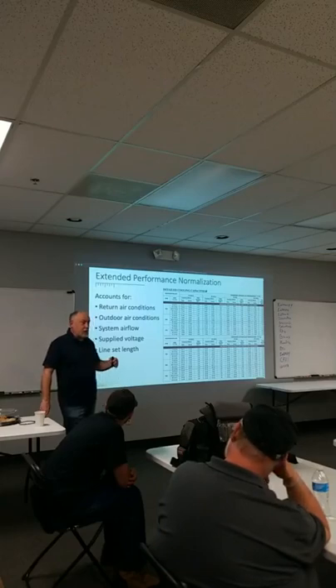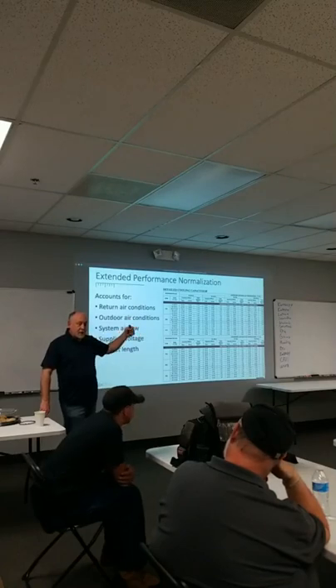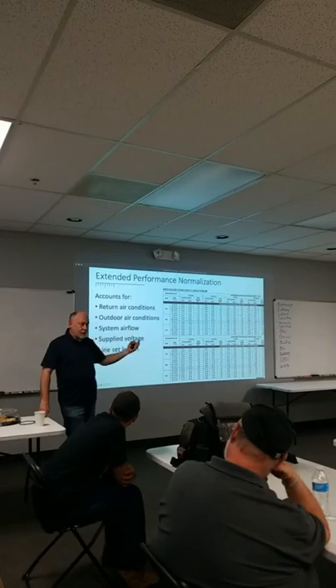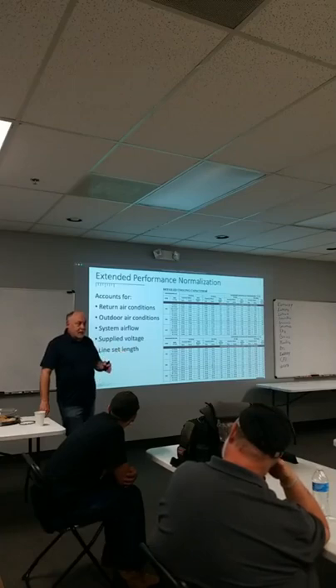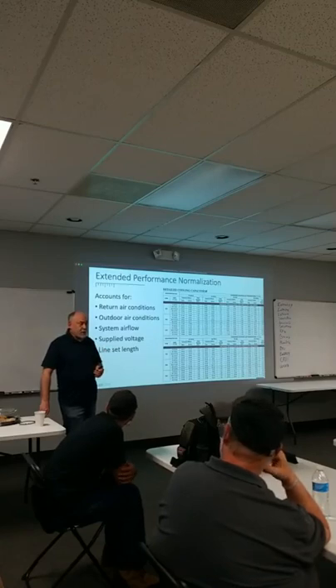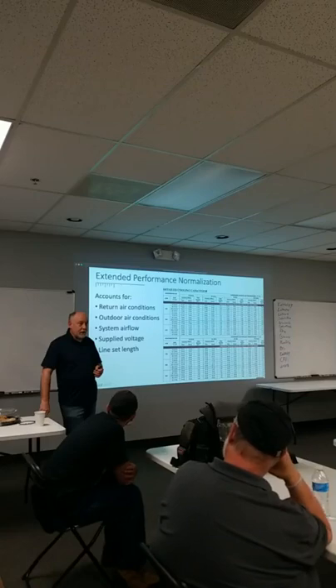So if you're at 240, right, think about a dimmer switch. You're turning up the light, you're turning up the speed of the compressor, you're gonna get more capacity. You're at 208, you're gonna get less capacity. Now, the equipment is also engineered to have a certain length of line set, typically 15 foot of line set. If you have a 15-foot line set, you'll get 100% of your capacity. If you have a 150-foot line set, you're gonna lose some. Every foot of line set is gonna cause additional losses of that equipment.